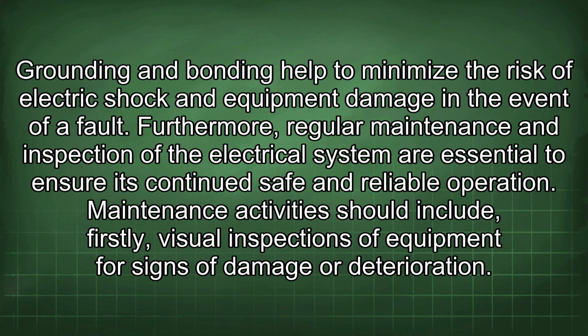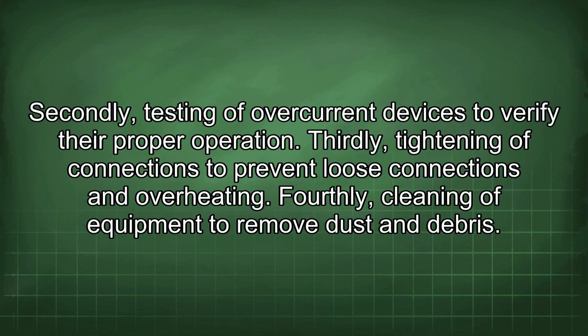Maintenance activities should include, firstly, visual inspections of equipment for signs of damage or deterioration. Secondly, testing of overcurrent devices to verify their proper operation. Thirdly, tightening of connections to prevent loose connections and overheating. Fourthly, cleaning of equipment to remove dust and debris.